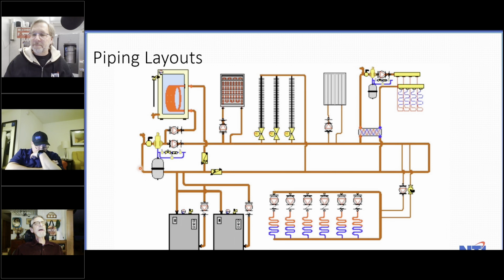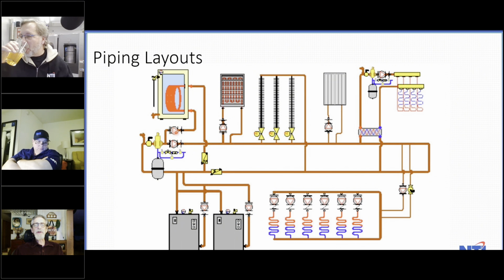At that point, we go around. We have an indirect tank with its own pump. So in the summer, those boilers are not trying to heat the entire primary loop. They will only heat that indirect tank. So the primary circulator would not run, just the indirect circuit. And then we've got closely spaced T's off to an air handler.